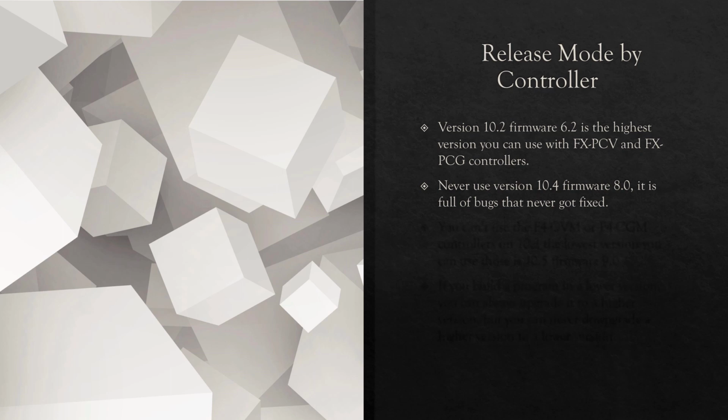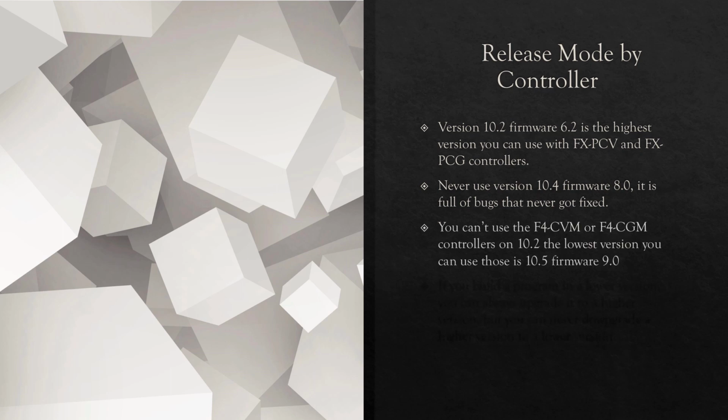Don't use 10.4. It's gone now. If you buy a new license of CCT, it doesn't even come in there. But 10.4 was full of bugs. There isn't a supported version of 10.4 anywhere. So if you have 10.4, you're having problems, and you see that that's loaded at 10.4, just upgrade that controller.